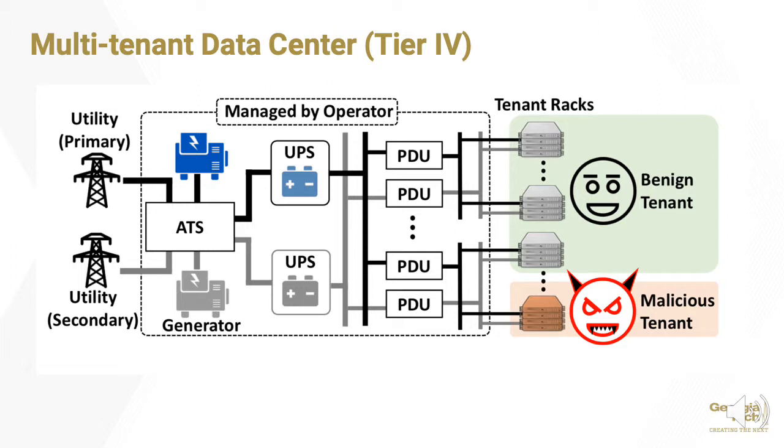As you can see, each rack has multiple power supplies going into each server. So if one power supply is down, the other power supply is there to back it up. If an entire UPS goes down, the other UPS will come online and kick in. Same for the generators. But not all data centers follow the same redundancy as was mentioned in the previous slide. And redundancy protection is actually lost during power emergencies, which is extremely dangerous and can increase an outage by over 280 times compared to when fully redundant.